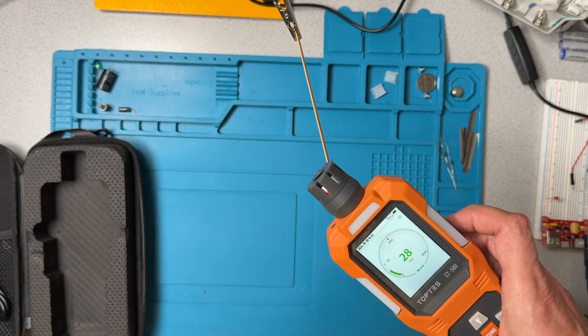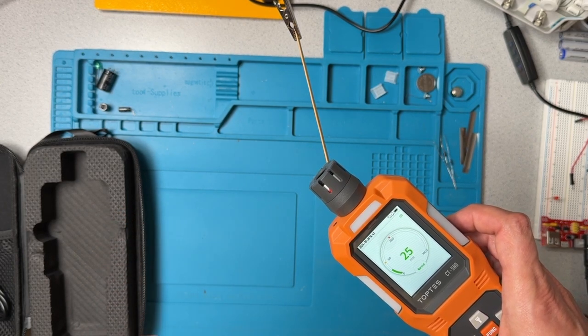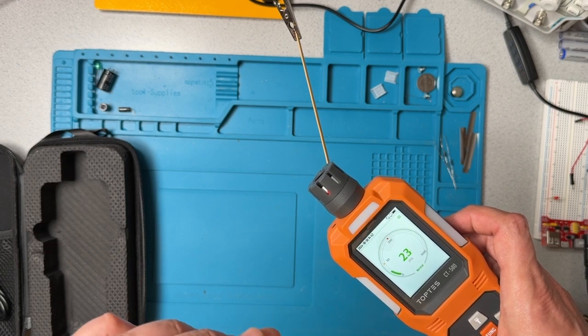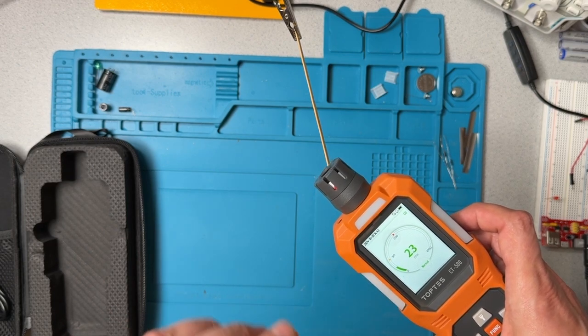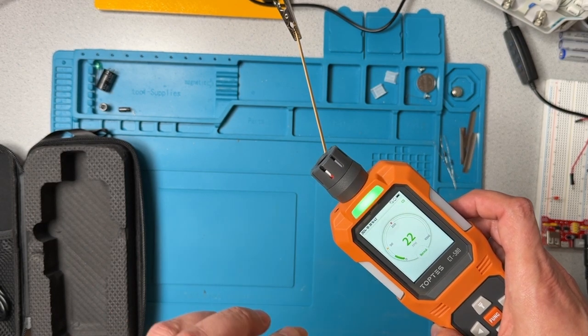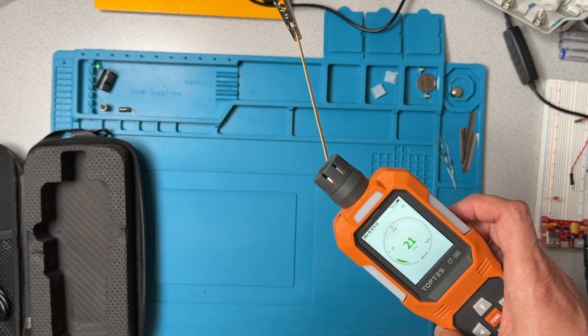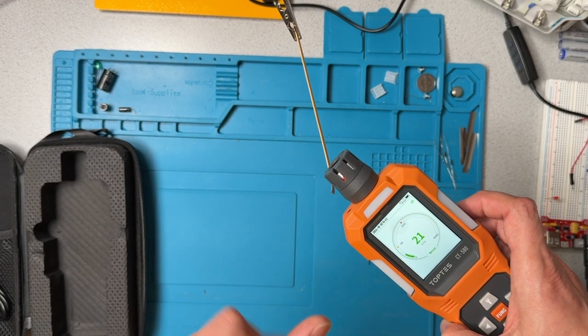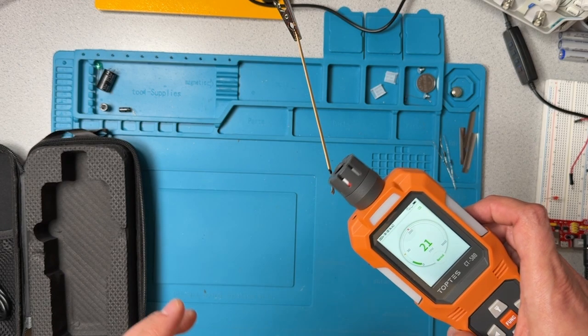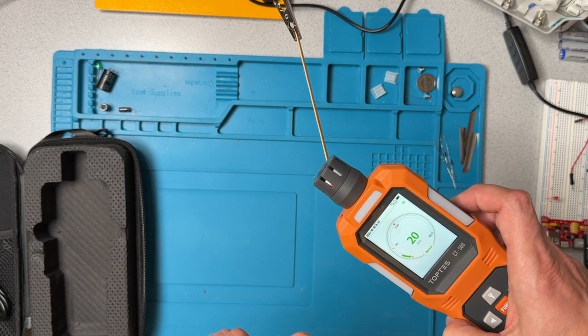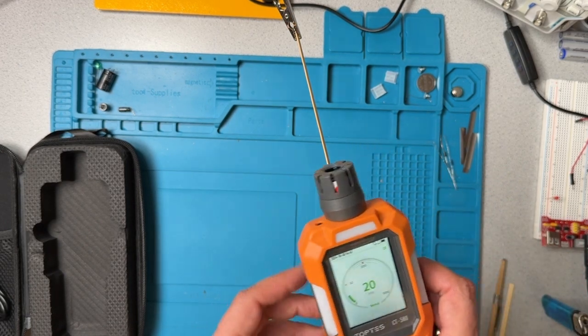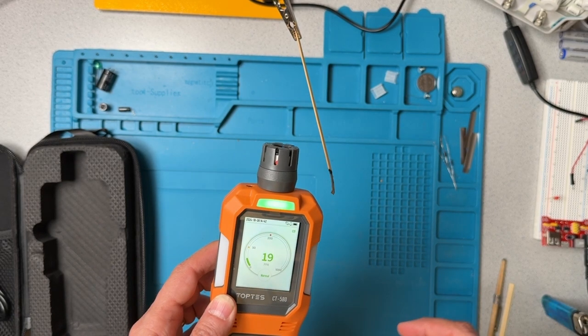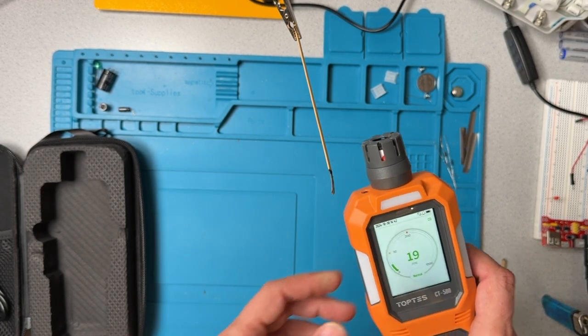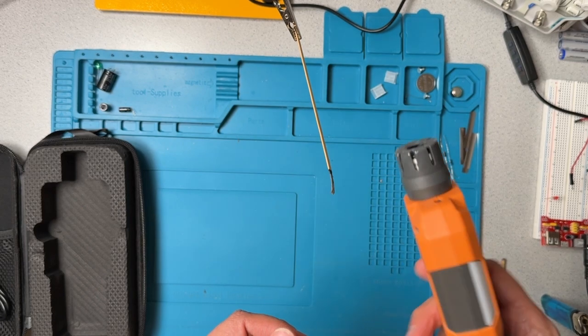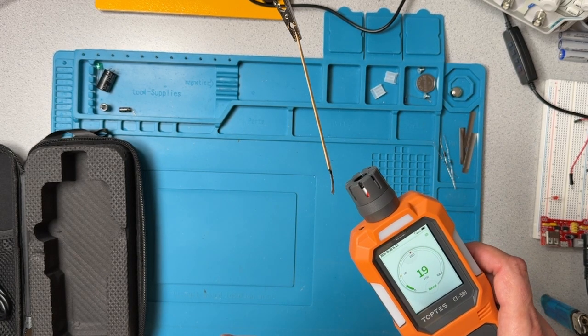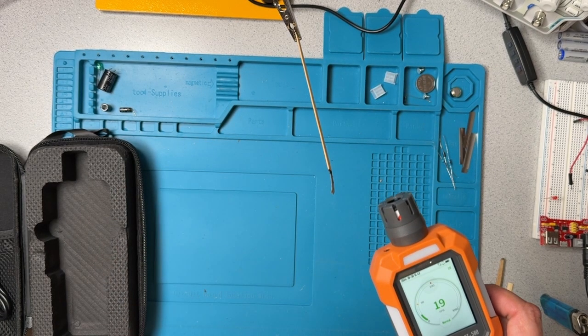And you might have noticed that when it went a little bit below 50, about 48 I think it was, the alarm didn't go off, and that was because of that backlash setting that we had set earlier in the configuration. And of course it's taking a little bit of time. There might be a little bit of smoldering going on there. But that's how that works. And so you can see that the unit is quite effective. Detects carbon monoxide, I would think, extremely well. That worked better than I thought it would.